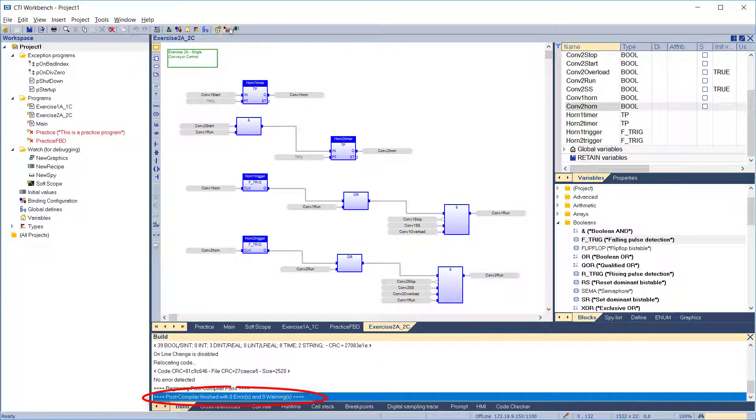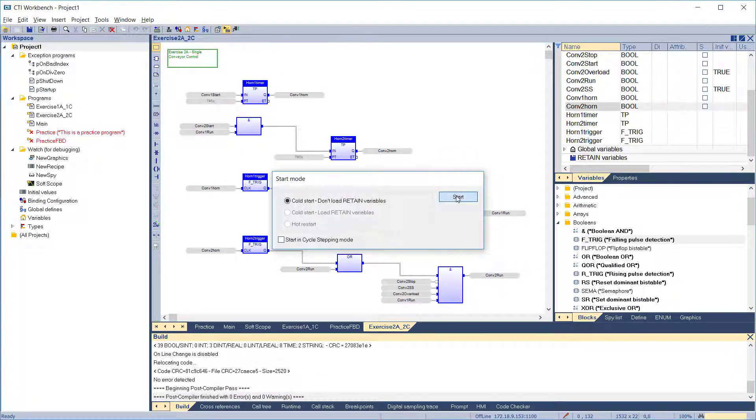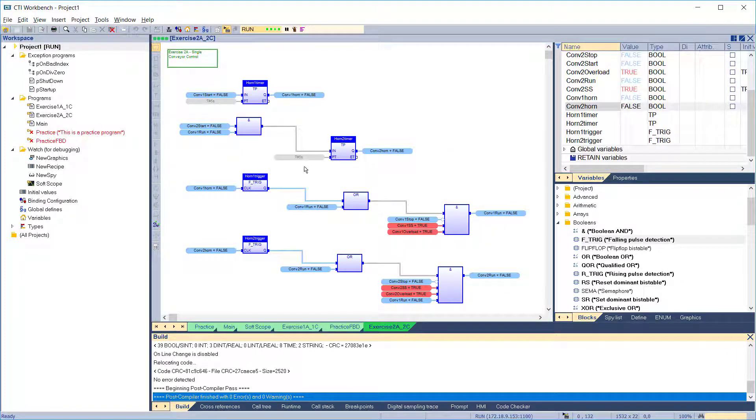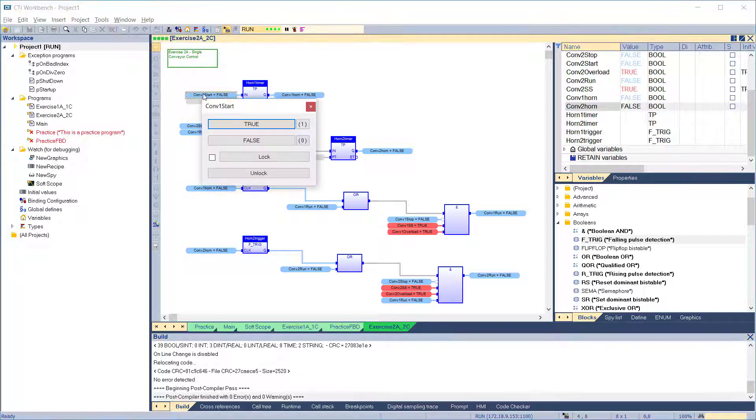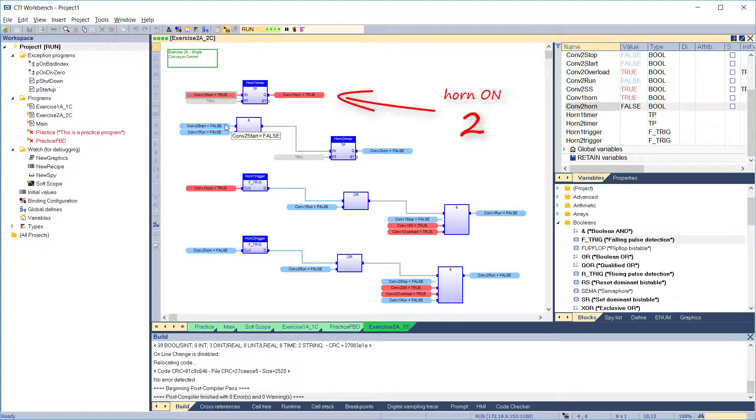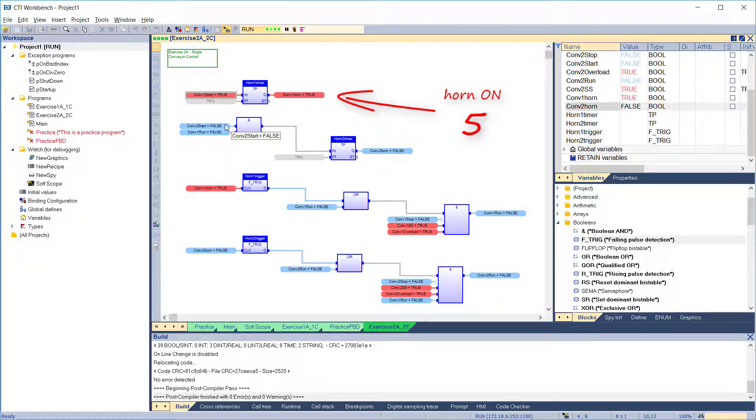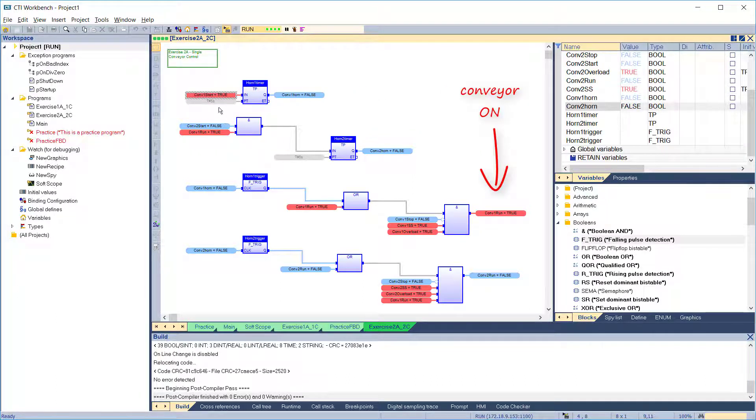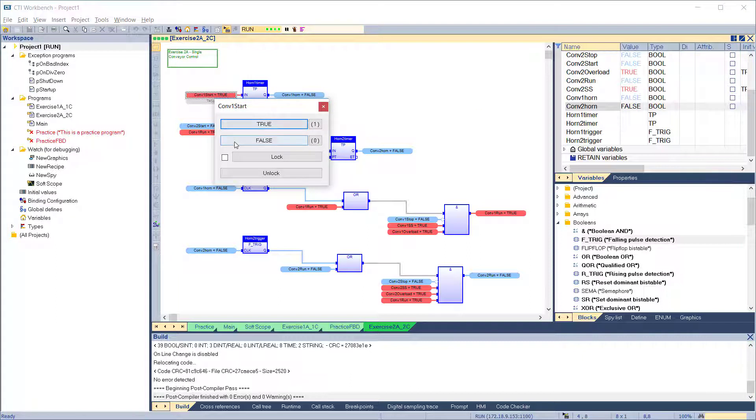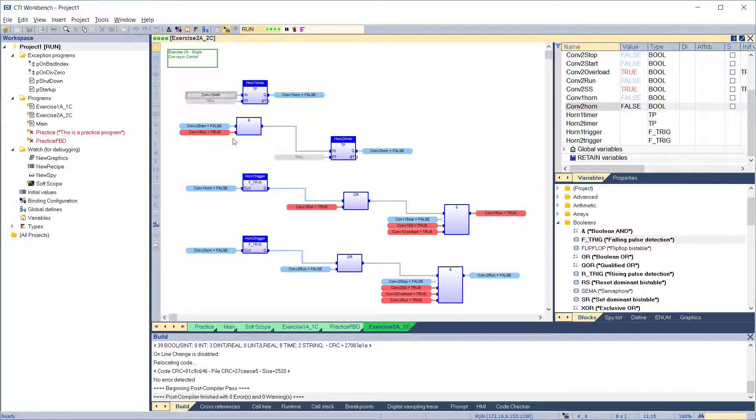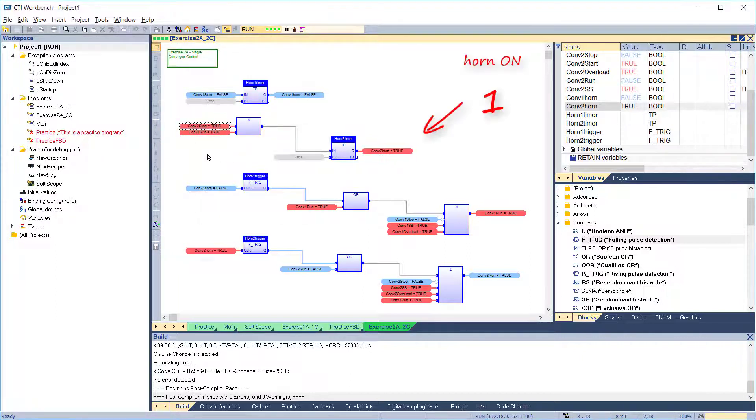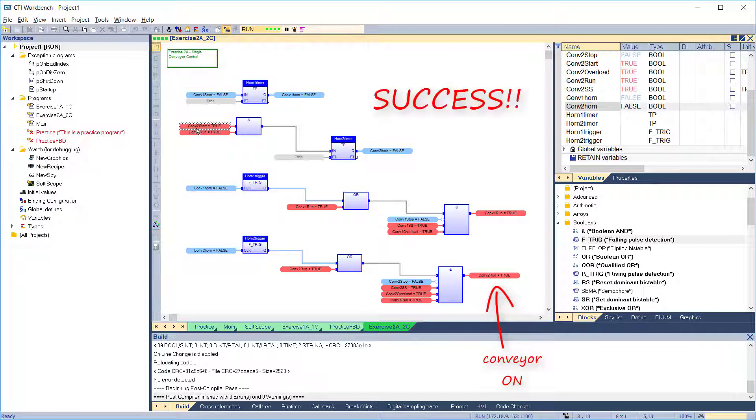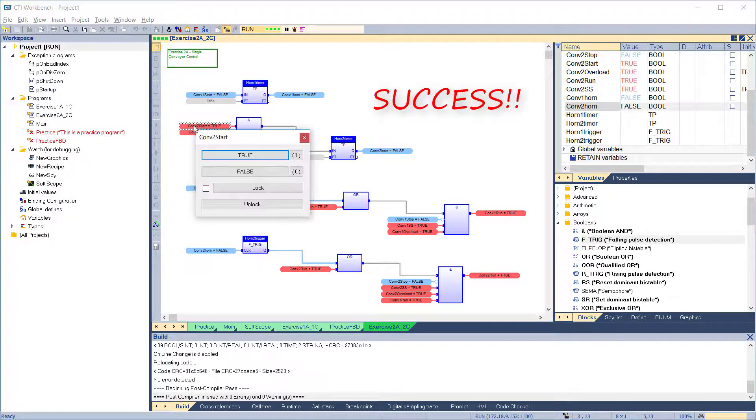No errors, so go to simulation. To test our completed program, we'll turn on the conveyor 1 start switch. If everything is working, we should see horn 1 come on for 5 seconds, then horn 1 goes off and conveyor 1 comes on. That's exactly what happens. Conveyor 2 should operate the same way. And it does. Another successful application.